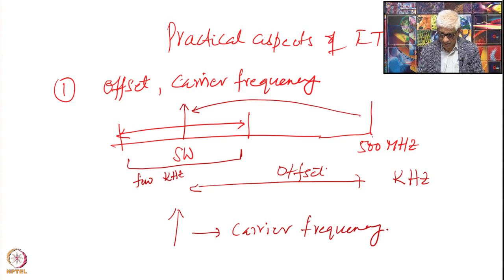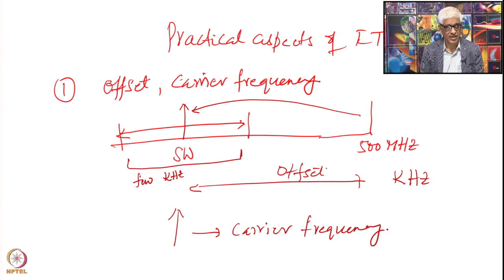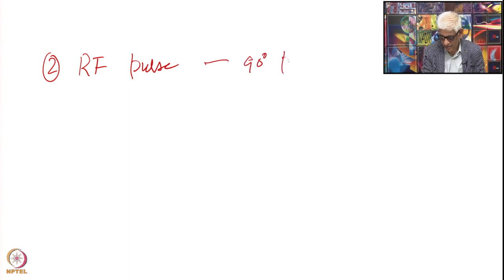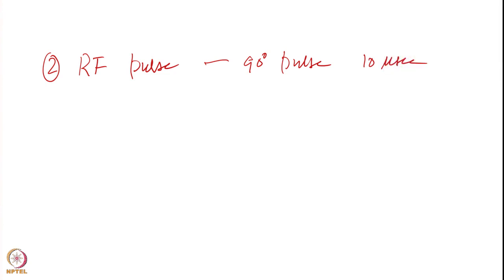The spectrometer frequency is the main frequency, but when I shift it and bring it to the center of my region or one end of the region, that is called the carrier frequency. The amount by which I shift is called the offset. The next parameter is the RF pulse — we said we have to apply a 90-degree pulse. This may be, let us say, 10 microseconds, and you must control it very well. It has to be exactly 10 microseconds, not 11, not 10.5. Perfect control is required in this RF pulse width.